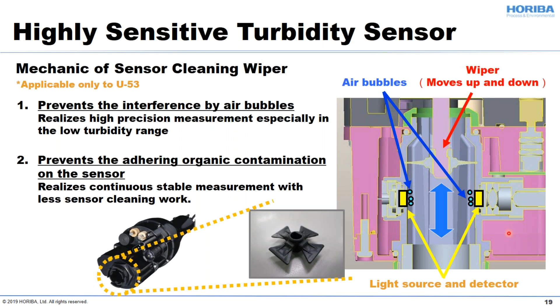And this is only U-53, but U-53 has a wiper function inside. It's moving automatically while the meter is powered on, cleaning the sensor to reduce maintenance work. By this function, the sensor can avoid interference by air bubbles, which may affect especially the low turbidity range. And by the continuous movement of the wiper, organic contamination is also always removed. So from this kind of work by the wiper, U-53 can measure turbidity with very high sensitivity.